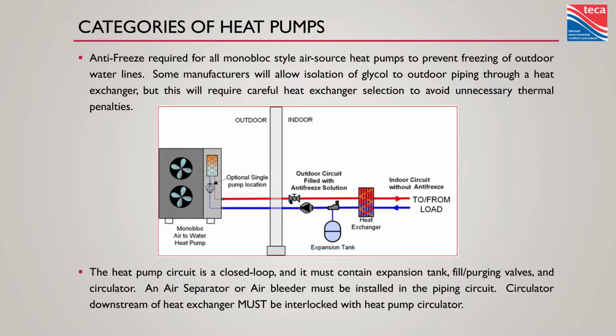On top of that, heat pumps want to move more water than we're used to. We've kind of come to this agreement now that forced air systems, if you go from an oil furnace to an air-to-air heat pump, I hope you're adding duct runs. We've accepted that we're dealing with a little less temperature rise for a higher volume of flow.